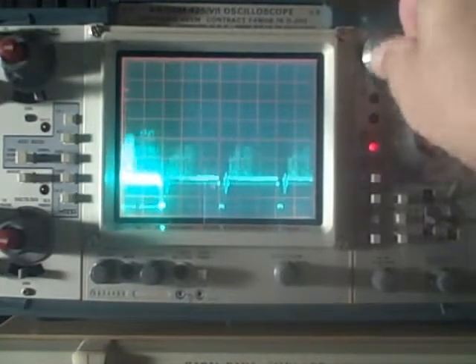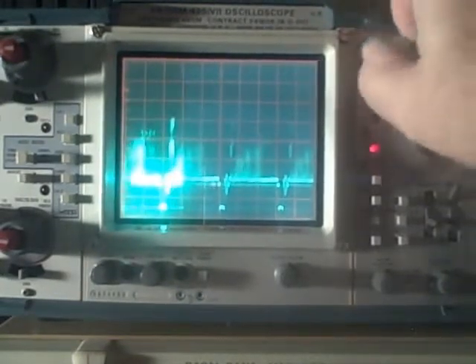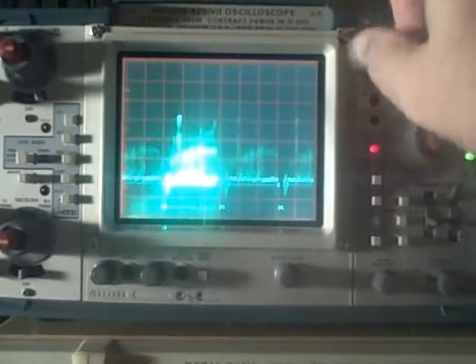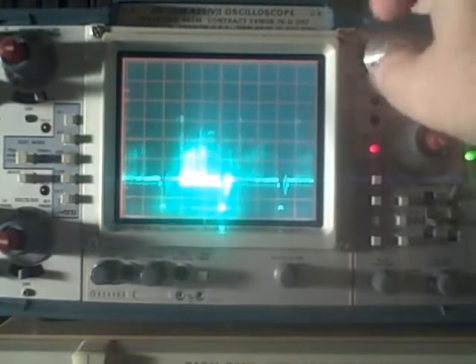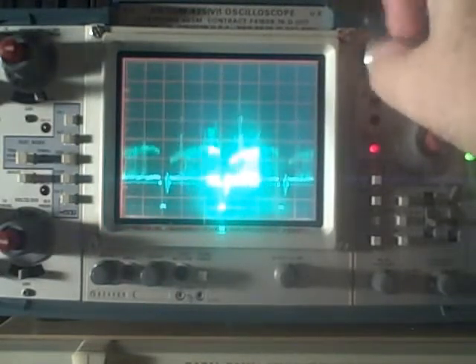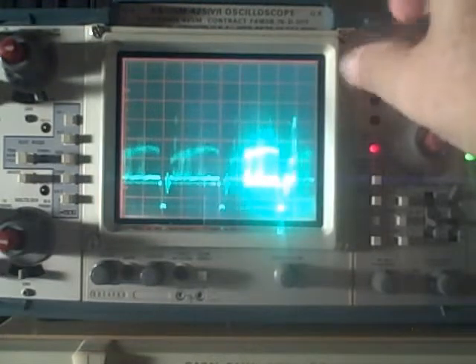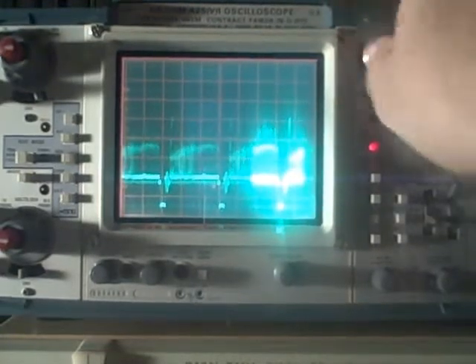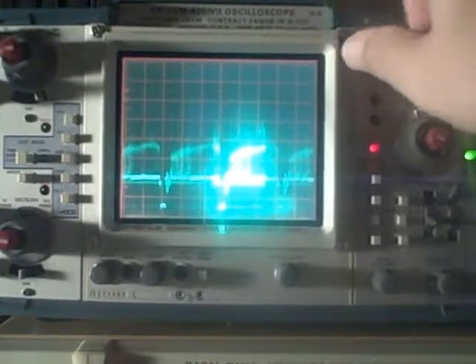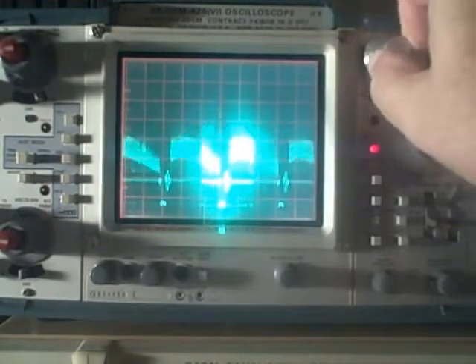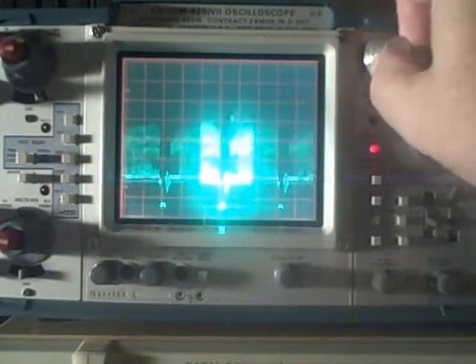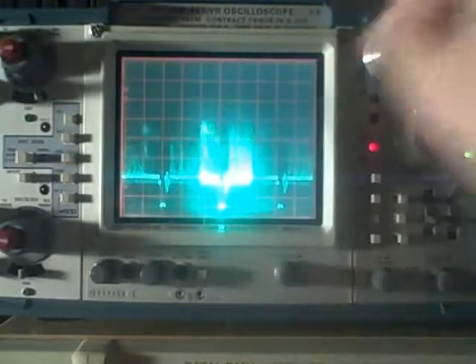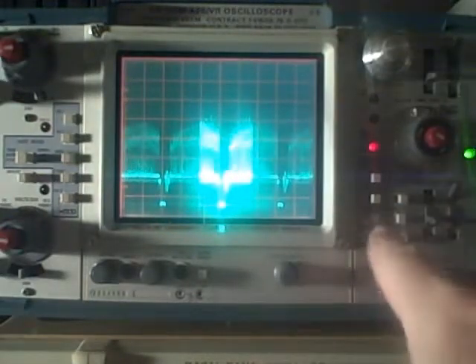using my knob up here, I can move where that brightness sits over my A channel waveform, my A time base waveform. And what I'm doing is I'm saying, gee, I would kind of like to examine this region right here. So I'm centering it on that, and I'm going to now push my B delay.